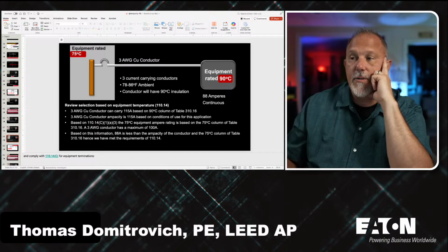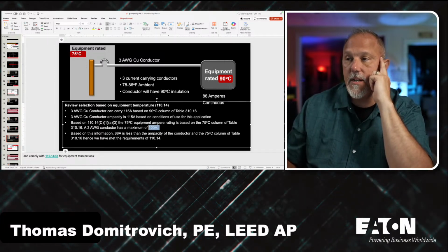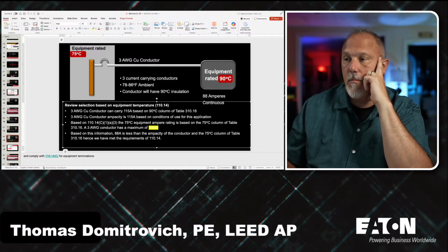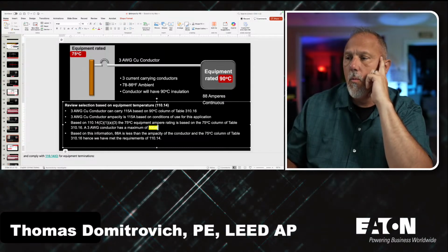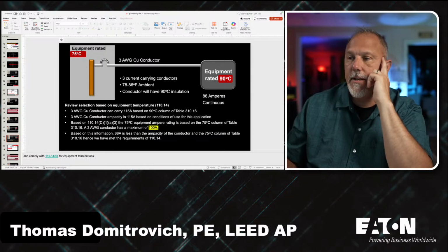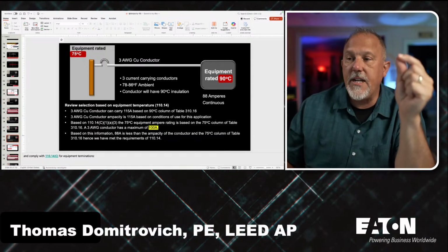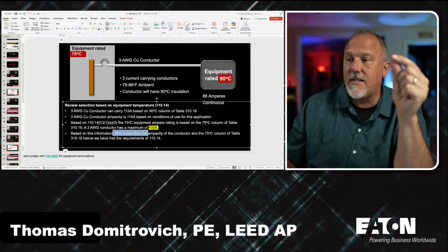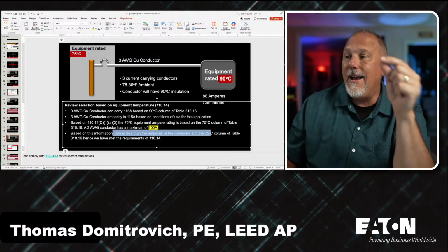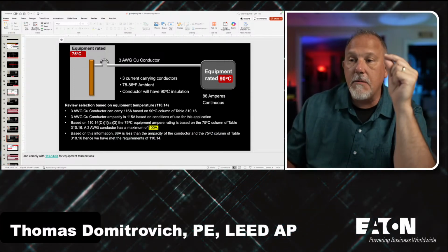I have to use the 75 C column, which is 100 amps. And I'm just going to highlight that. There it is. And then I say, based on this information, 88 amps is less than the ampacity of the conductor in the 75 C column of table 310.16.